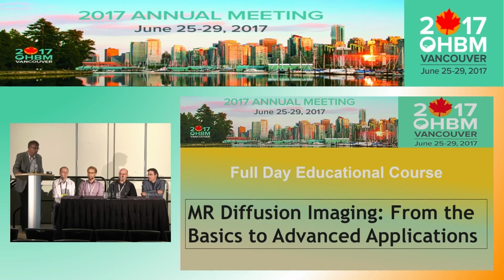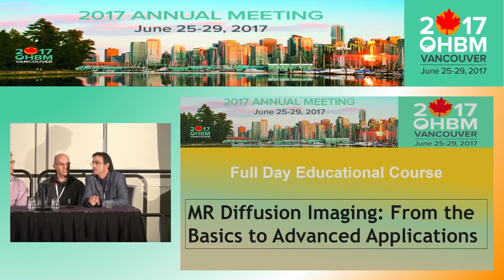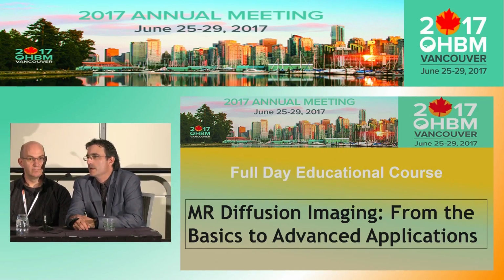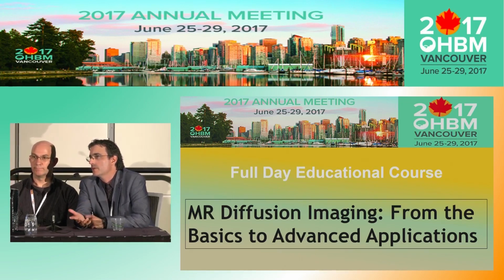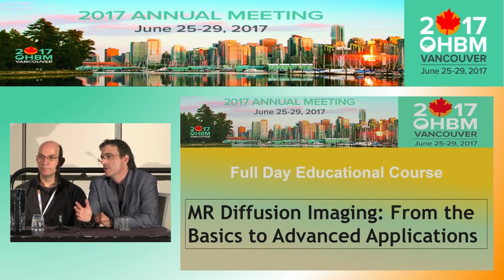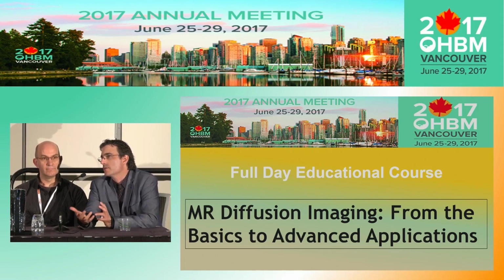I'm not familiar. Yeah. I mean, there's different. I think one of the studies was using some type of iced water phantom. I mean, you can use a phantom where you expect a certain diffusion coefficient, and you get that out. And then the problem is if you have an isotropic phantom, you'll get the low FA value, but you're mostly looking to get the mean diffusivity is all equivalent, and then assuming that your gradients are performing fine, everything's still working. And so there are other chemicals as well that have ADCs similar to human brain, around 0.8. So there are some available as well.